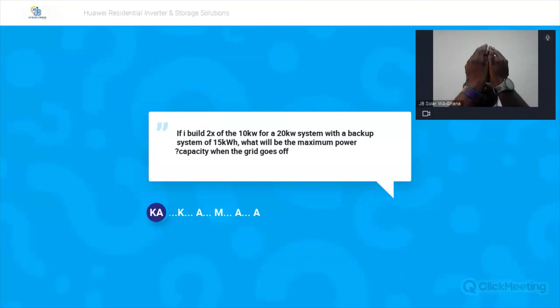The maximum discharge from the battery system is 5 kilowatts. Take note, it's 5 kilowatts. So what you can do is create two systems: one 10 kilowatt with 15 kilowatt hours, another 10 kilowatt with 15 kilowatt hours. Each one has its own backup box. Then you connect the system to different critical loads. Each critical load can benefit from 5 kilowatts, another critical load can also benefit from 5. That is possible. But when you combine the systems together thinking you can get 10 kilowatts from the system, no, it will not work.